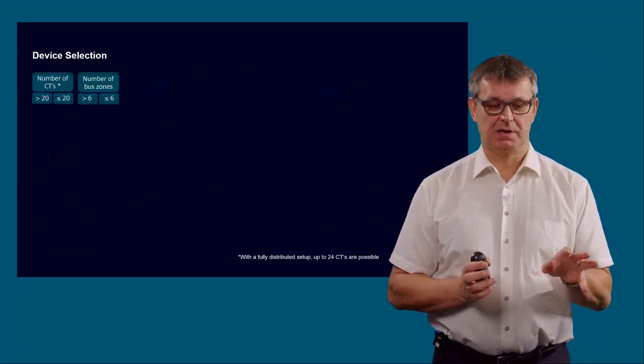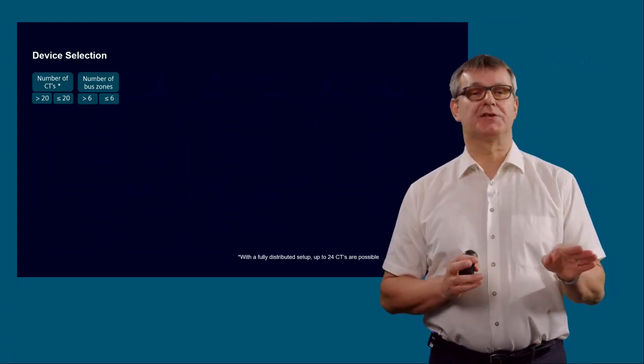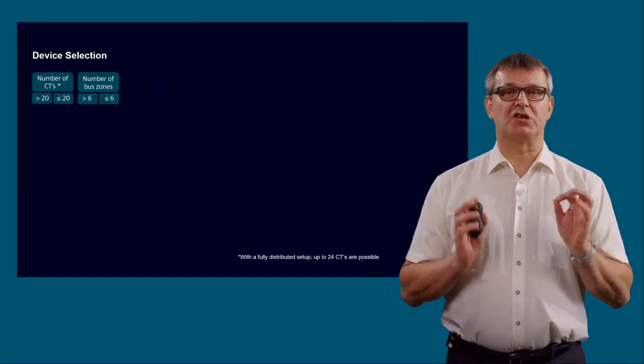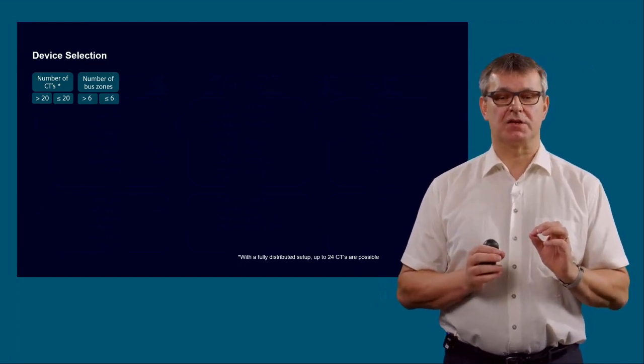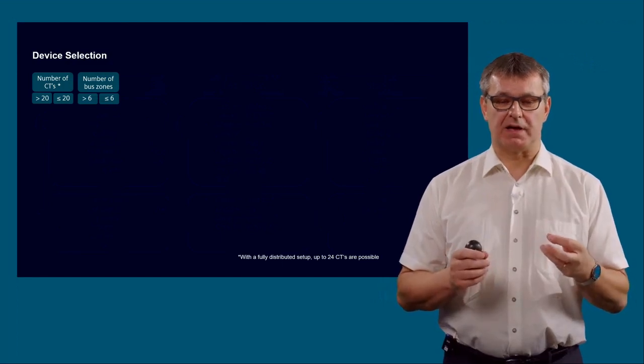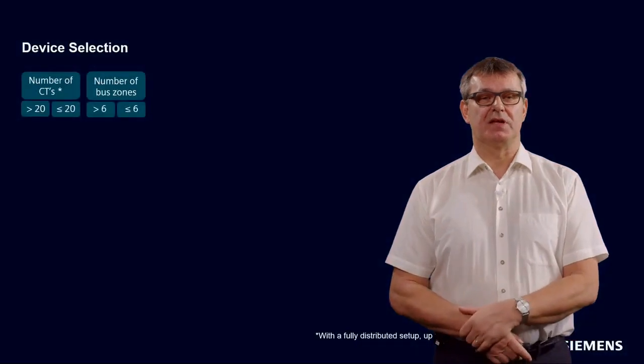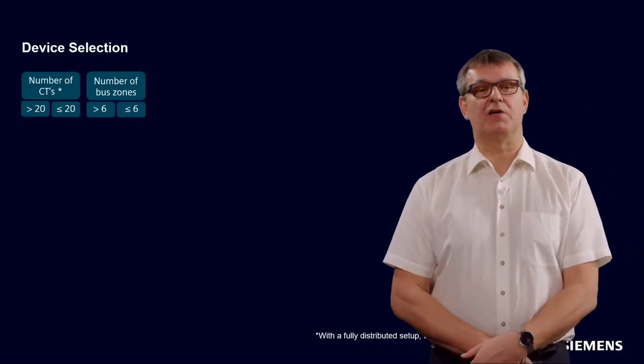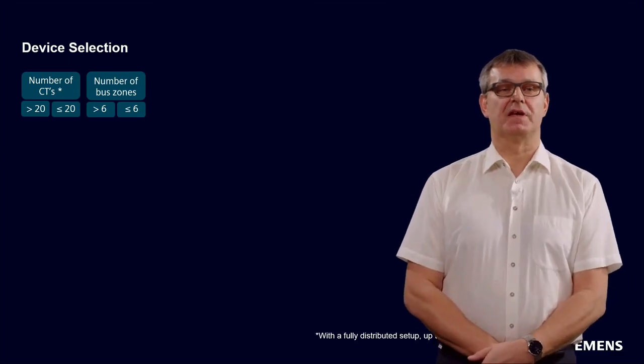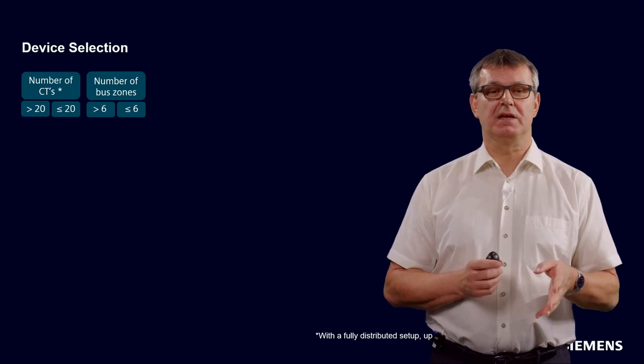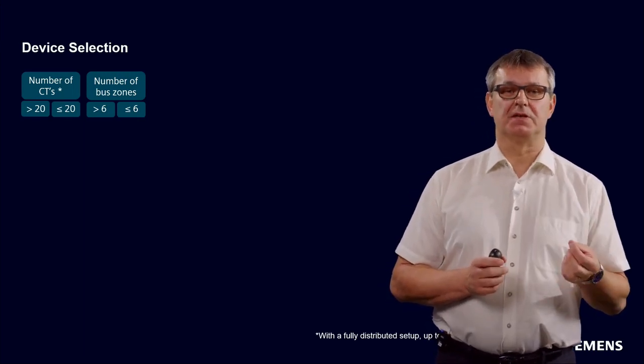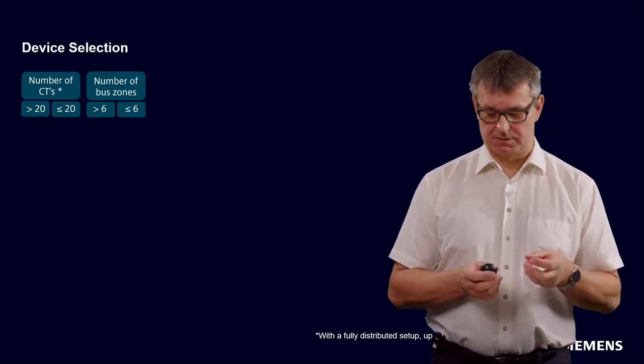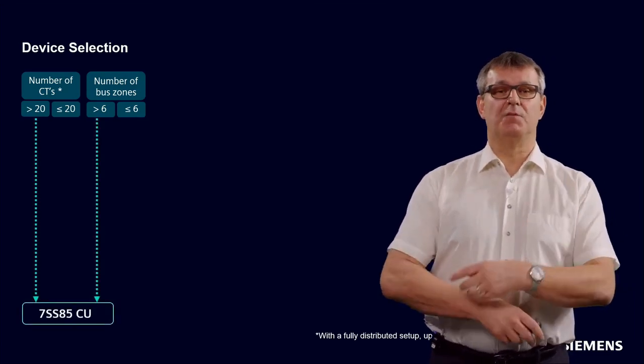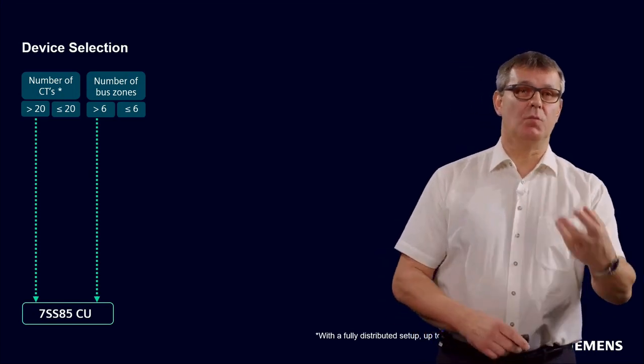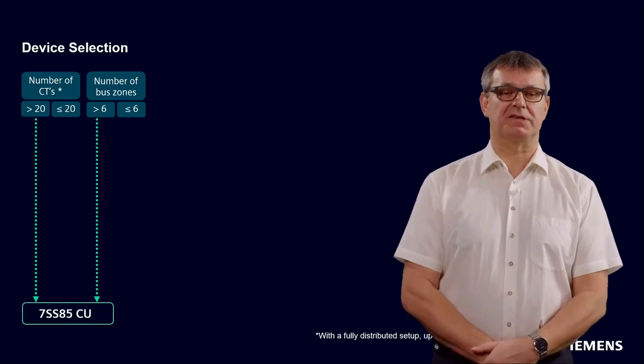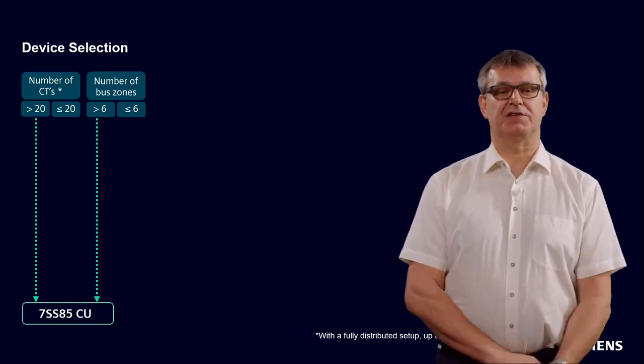What could a decision matrix be for the correct device selection, to select the correct type of 7SS85 busbar protection? The first question is, what is the number of CTs? What is the number of measuring points? Are they higher or lower than 20? And what is the number of independent busbar zones? Are they higher or lower than 6? If you have more than 20 CTs and you need more than 6 busbar zones, there's no doubt about it. The only solution could be to use a 7SS85 CU.